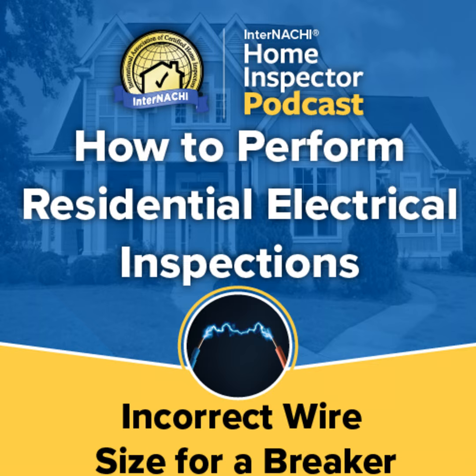Looking at the table, we see that a 12 gauge wire is the minimum size for a 20 amp breaker. The wire gauge is permitted to be bigger than 12 gauge when connected to a 20 amp breaker. A 10 gauge wire is the minimum for 30 amp breakers. You can't have a wire smaller than a 10 gauge when it is connected to a 30 amp breaker. A wire gauge that is smaller than the minimum size for the breaker is vulnerable to overheating. Oversizing the wire for the breaker is allowed.